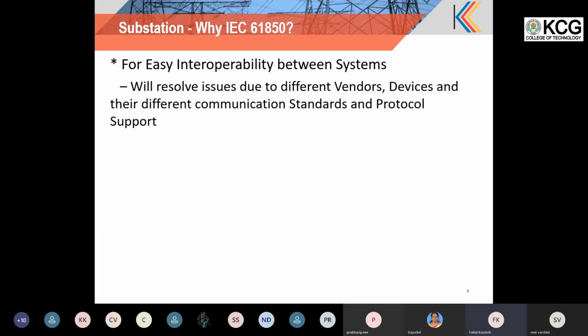The first thing is, when they formed the standard, they wanted complete interoperability between devices, irrespective of vendor. It can be ABB, GE, Siemens, or any other equipment manufacturer. For one function, if a Siemens IED is selected, for another function a GE IED can be selected, but they want complete interoperability between the devices, and between devices and the monitoring equipment or monitoring SCADA. That was the prime aim of the standard. With multiple vendor tools and multiple different devices, we want complete interoperability between all the systems. That is the prime aim of 61850.